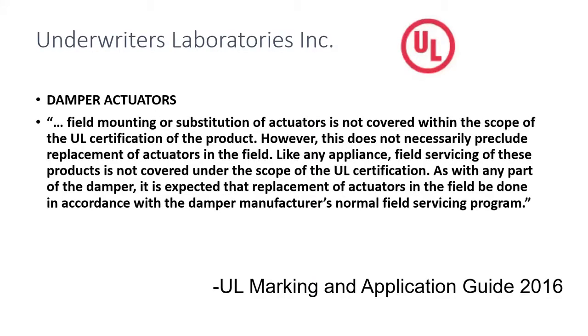So here's what UL says about replacements. I don't want to read it to you, but two key points here. One, it refers to a damper as an appliance. Actually, in this one it doesn't, but their previous version did. It refers to it as an appliance, and it can be treated just like one. People aren't afraid to change gas valves, which are handling a dangerous explosive mixture, and they don't get CSA certification or UL certification. They don't need it. You can repair things in the field, and UL is stating here in their marking guide that you can replace actuators in the field. Same thing with the high temperature limit. Yeah, they're practical. They know that stuff's going to get replaced. The idea that you'd have to replace the entire thing because of one component is a fallacy.